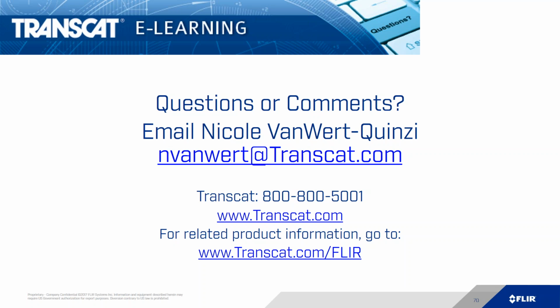Okay. What is the typical accuracy of the IR cameras? All right, so accuracy of IR cameras can be described in a number of ways. The first way is the general design specs that we as manufacturers build. And I would say a majority of infrared cameras have plus or minus 2 degrees or 2%, whichever is greater. So if I'm measuring a 100-degree object, I have a plus or minus 2 degrees, which is 2 degrees. If it's a 500-degree object, it's plus or minus 2%, which would be 10 degrees. So we can measure 510 to 490.